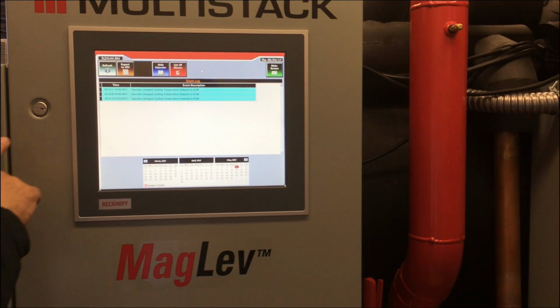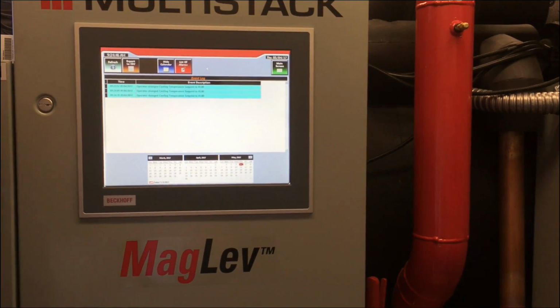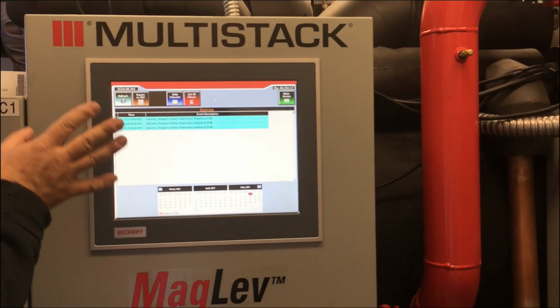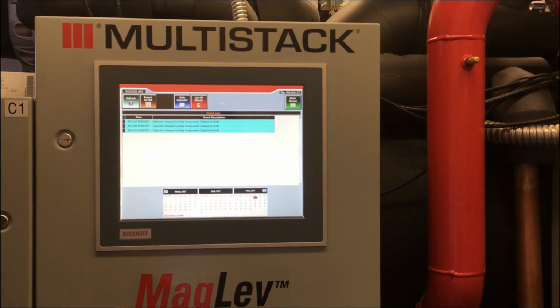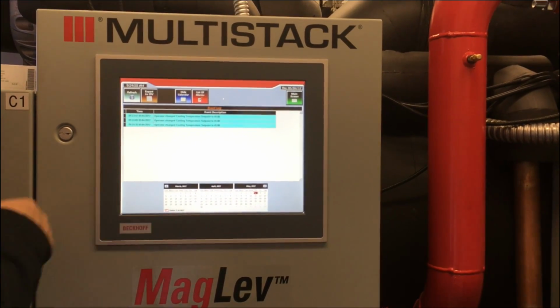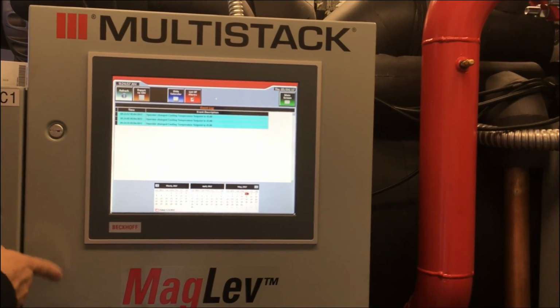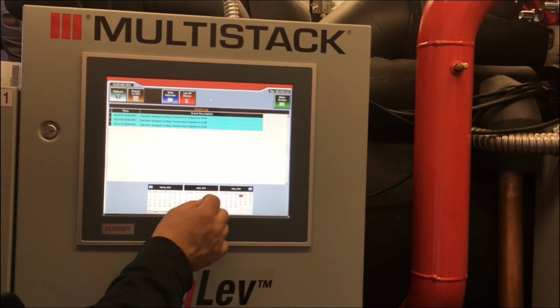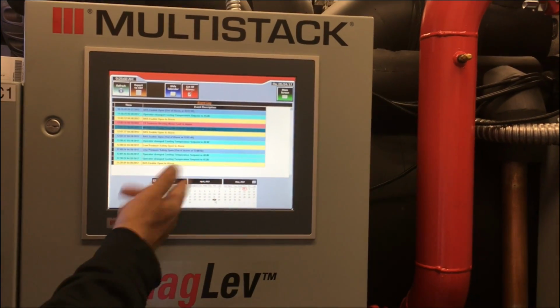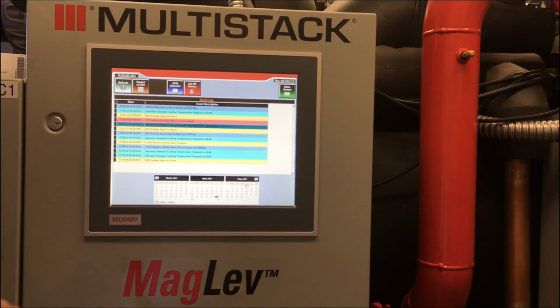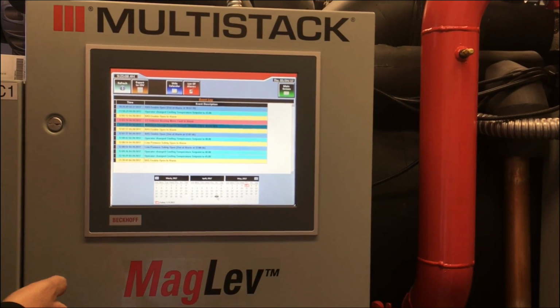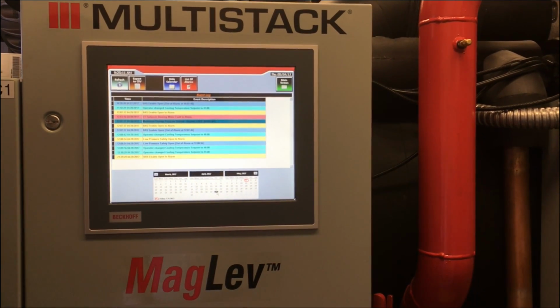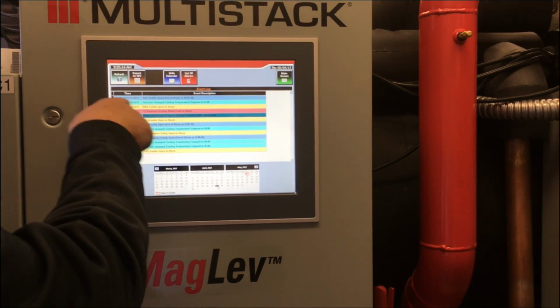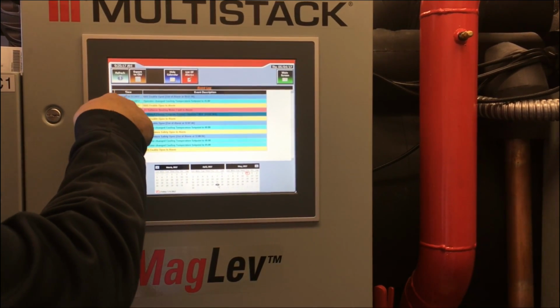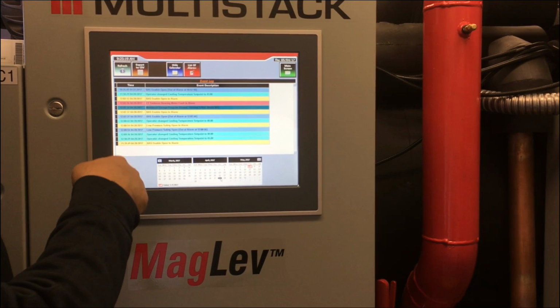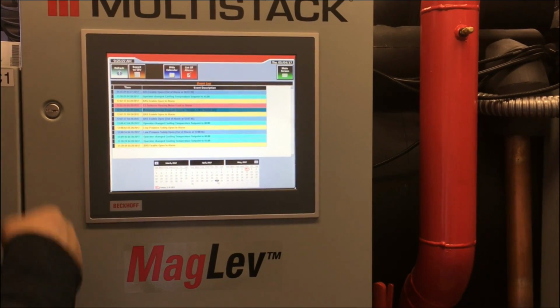So this records any fault, alarm, change set point, anything that happens this day will show up on this screen, and it's here forever. We have a memory card in here that stores this data for up to 10 years. And you can, as simple as going back and going, oh, this day was hot, maybe it was running that day. So we find a day, we can see what happened. It says it was open alarm, open alarm, let's see, our first out of alarm is at 1846. What happened at 6 o'clock at night, looks like it turned off for the first time, must be based on demand or temperature, or any of that.